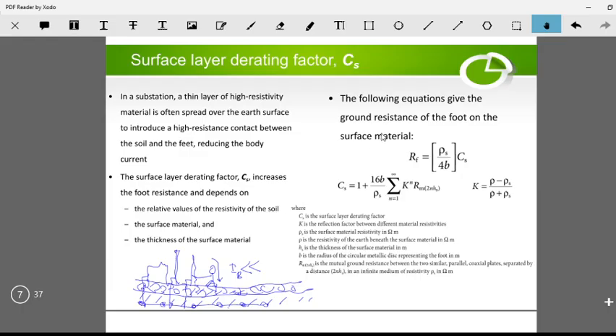With this surface derating factor C_S, you can define the foot resistance R_F. Earlier we had rho over 4b, where rho was the resistivity of the earth, but now before the earth you have the surface layer with resistivity rho_s. So now you have rho_s over 4b, multiplied by this derating factor in order to calculate the foot resistance, because now it has been increased.